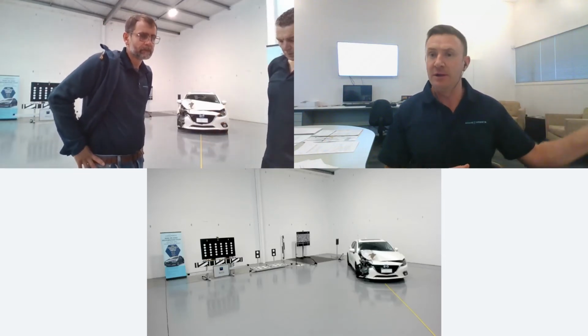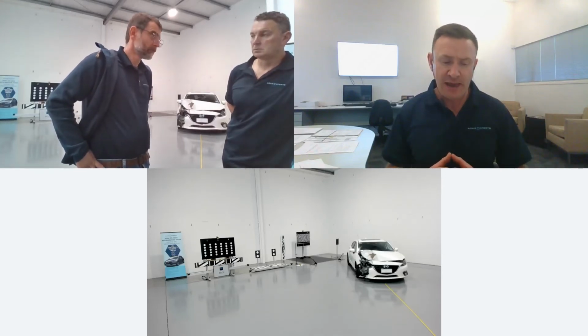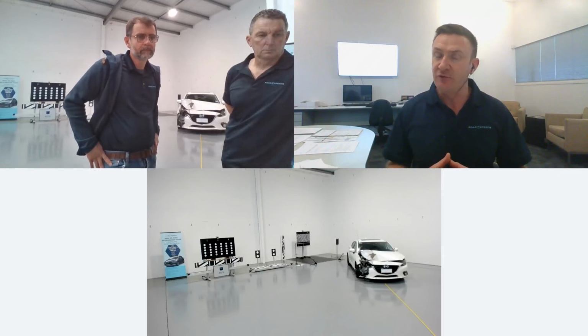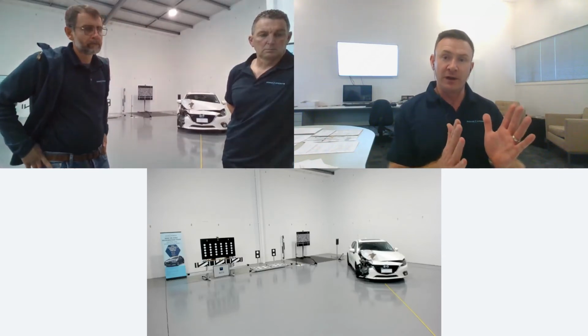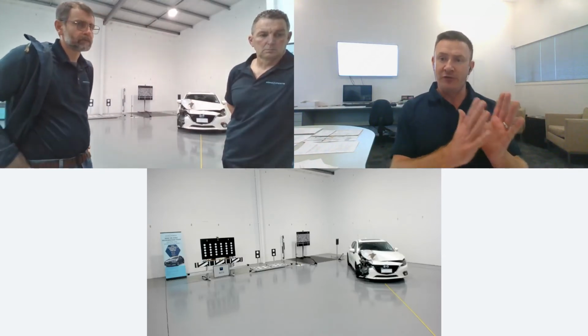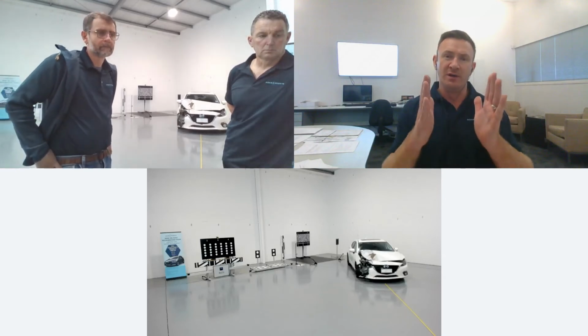And just on from that, next Tuesday we're going to have another one of these sessions, so we'll certainly send an invite out to you all. What we propose to do there is show the influence of not having the correct space or having objects in the space. We'll perform a read and a reread with something in the space and show you just how different the readings can be. Because what we can also achieve, and it's quite a scary thing, is what we term a false positive. You can get a calibration achieved because it's in the window of where it's looking, but it could be well outside what you would call accurate. And then that leads to problems.